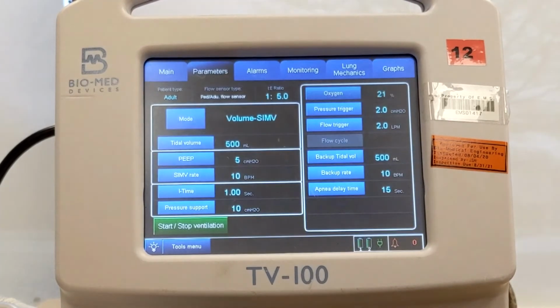As we already know, in SIMV mode, the TV-100 will deliver manual, mandatory, assisted, or spontaneous breaths. The clinician will choose between volume control or pressure control for these different types of breaths. The assisted breath period represents the minimum time between assisted breaths and will be determined by the set rate. In SIMV mode, the clinician is able to set the rate, I time, PEEP level, and trigger sensitivities. Apnea detection is required in this mode.